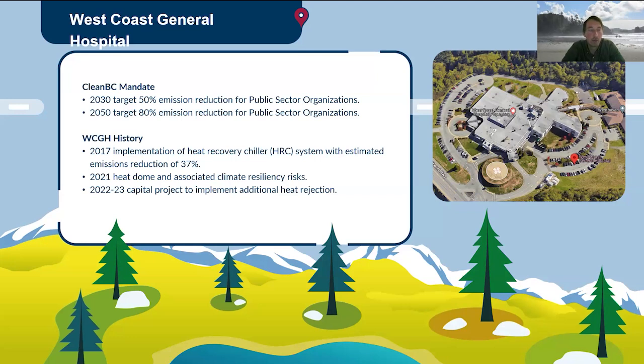Back in 2017, we implemented a heat recovery chiller system with an estimated benefit of a 37% emission reduction. We did not get any of that benefit for this particular project. We had some issues and challenges with that, and those really became pronounced back in 2021 when we had a heat dome in BC, and the challenges of the system were also on the rejection side. So we weren't able to actually get heat out of our building. We had a system that needed a lot of attention. And so we put in a capital submission to put in a new cooling tower to help support the site in being able to respond to future weather.